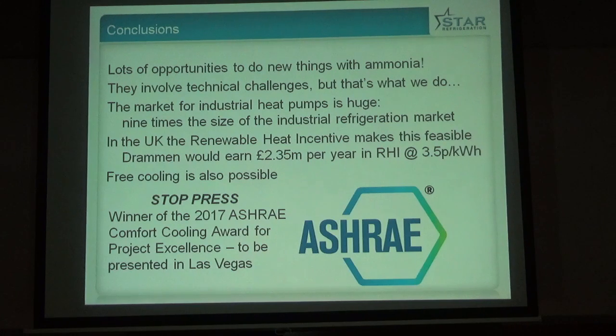But in an application like this, which is an industrial plant by any description, it's bigger than most of the systems that we build for the industrial market. Safety is not an issue. It has very, very good environmental performance, because it's zero ozone depletion potential and zero global warming potential, and there isn't anything else that fits that bill. So really fantastic from that perspective. And for all of these reasons, efficiency, reliability, maintainability, ongoing lifetime performance, it's a good choice. So if you were to rule it out because it's flammable and toxic, you wouldn't really be doing yourself any favours. The difficulty is exactly as you said, getting that message across to people.